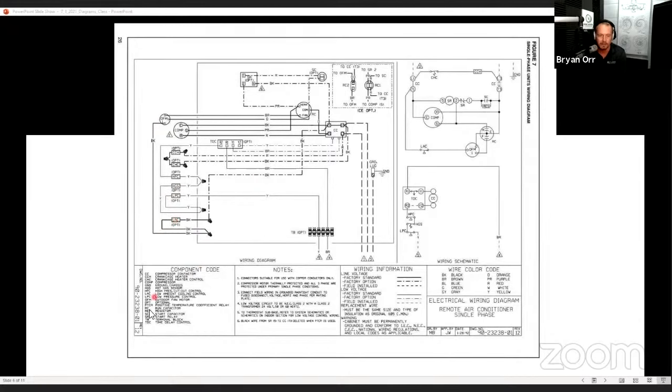But see, again, you wouldn't know that because this doesn't show that it's connecting directly to T3. It just shows like here, that could be a wire nut for all I know, right? Because this diagram isn't concerned with specifically how it's connected. It's concerned with electrically how it's connected. Because electrically, everything that's along this line is the same, right? Electrically, there shouldn't be any significant resistance. So these should all be the identical point. But only when you come over here and you pay attention to where it's connecting, do you know exactly where that point is, which is why they call it a connection diagram or a point-to-point. Point-to-point, connection-to-connection. And then in addition, we know, okay, this is going to be a red wire.